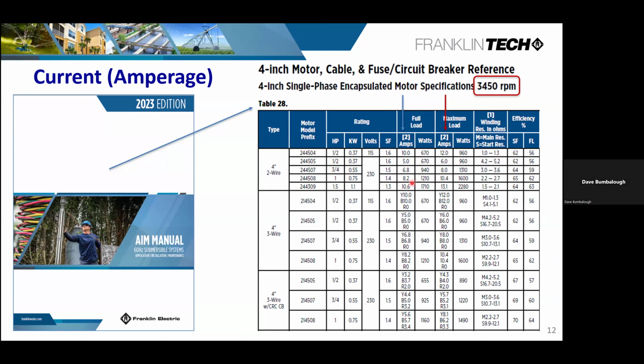Okay, so if you remember back in the calculations we were looking at in the earlier presentation, where I was showing you the horsepower formula, where you took your flow times your TDH, you divide it by the efficiency, and then that 3960 constant gave you, in that exercise, a 2 horsepower. So on a 2 horsepower, I would expect, I'm not showing one here, but I would expect that the 2 horsepower range would be in its full load amperage range here. So when I clamp onto it, I would expect to see that motor pulling that amperage in this area here. If it's not, then I want to start looking for some issues.